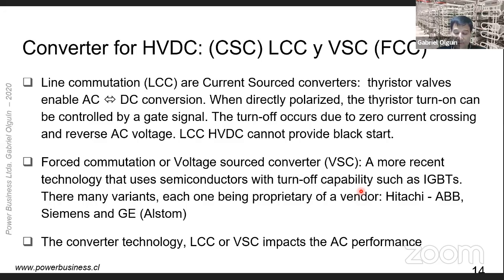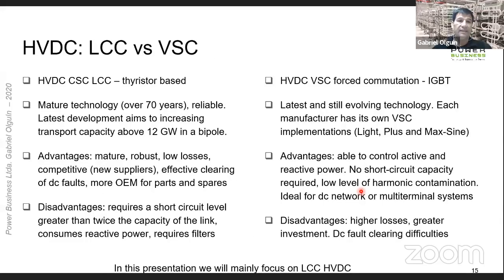VSC stands for voltage sourced converter. VSC are force commutated converters that use semiconductor devices with turn-off capability, such as IGBTs. VSC is a more recent converter technology and is still under development. There are a few VSC variants, each one being proprietary of a particular vendor, in particular Hitachi ABB, Siemens, and GE. The HVDC converter, LCC or VSC, impacts the performance in the AC.